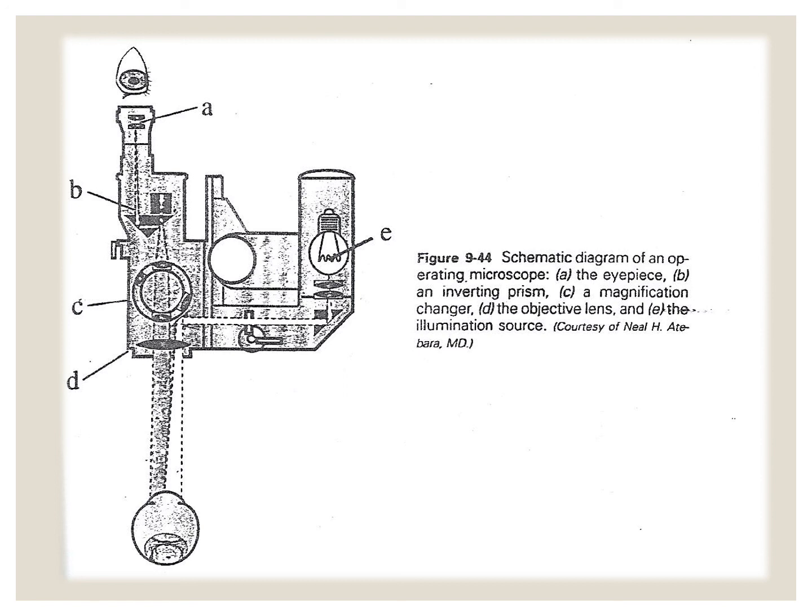There are other structures attached to this operating microscope, which are the illumination system that is composed of the halogen bulbs, as well as the beam splitter, which splits the illumination into two parts. Part goes to the camera or the TV in order to record the operation, and another part goes to the assistant or the side tube for the assistant to be able to follow up the surgeon and to see the steps of the surgery.